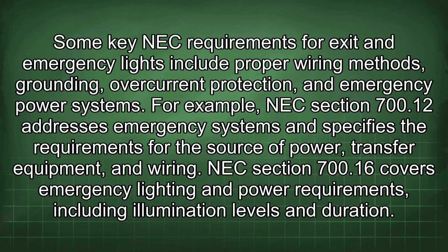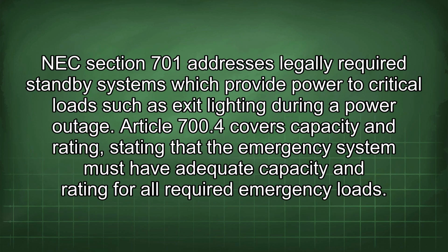For example, NEC Section 700.12 addresses emergency systems and specifies the requirements for the source of power, transfer equipment, and wiring. NEC Section 700.16 covers emergency lighting and power requirements, including illumination levels and duration. NEC Section 701 addresses legally required standby systems which provide power to critical loads such as exit lighting during a power outage.